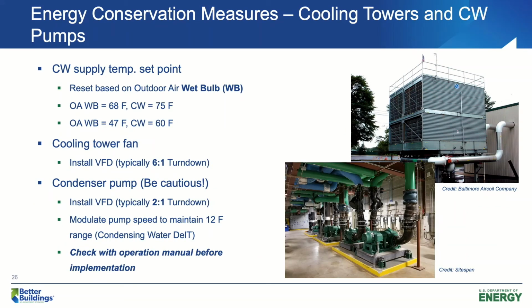Cooling towers, we can reset condensing water supply temperature based on outdoor air wet bulb temperature. When the outdoor air wet bulb temperature is low, we would like to take advantage of that. We would like to make cooler condensing water so we can make our chillers happy and give us a better chiller efficiency, less chiller energy. But at the same time, we do not want to set the condensing water temperature too low and make our fans run 100% speed all the time, trying to achieve something that is not even physically possible.